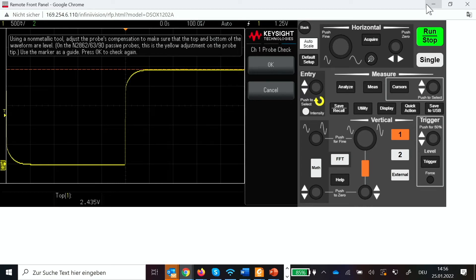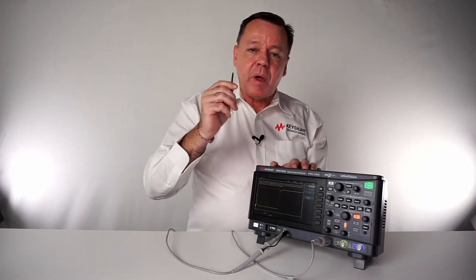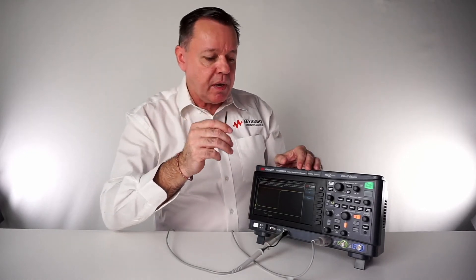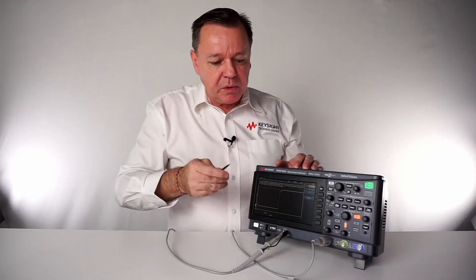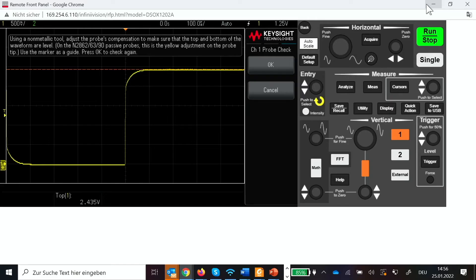And again we use the tool that is very important – it's a plastic probe screwdriver, not metalized. This comes with all the probes included with the oscilloscope. So now we adjust that.